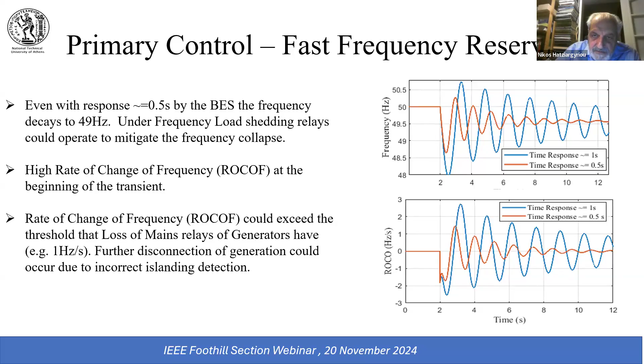So this is one particular case where it seems that you need to do more than just providing faster frequency response. And here is what, of course, all this severe frequency decay and the rate of change of frequency is due to the lack of inertia. In order to apply faster response, you emulate the inertia of the system. So you can add another control loop that emulates the virtual inertia, as you see in the block diagram. And the results are in the diagrams where this function, the droop plus the virtual inertia, the response of the battery is much faster.